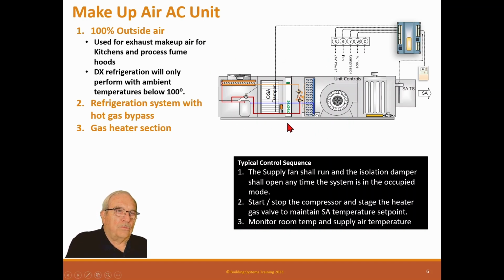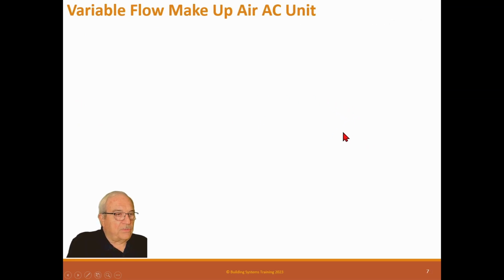One of the reasons these can work is we can gas this such that it can handle that higher temperature. It just won't be super efficient. If you're trying to do 68 degree air, it won't do that. It's going to be a problem. Maybe 70 degree air, no problem, because it's gassed with the higher temperatures. So you can do that. And they use these a lot in areas where they don't have real high ambient. There's a lot of places that have high humidity, have 95 degrees as the high temperature, so you can use those. So now we'll talk about a variable flow makeup air AC unit.